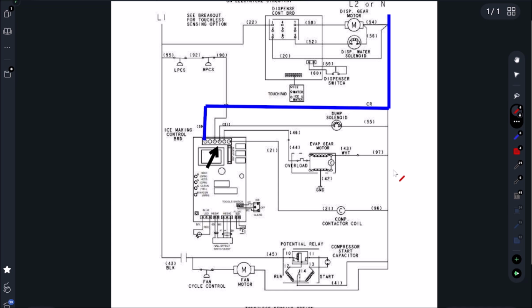All right, so because we have that 15-minute delay, I have to troubleshoot things extremely quickly. I want to get it on the first go around. So we came through here, low pressure switch is good, high pressure switch is good. Well, we jumped it out and we completed the circuit. How do I know we completed this circuit? Because the LEDs on the board did not go out.